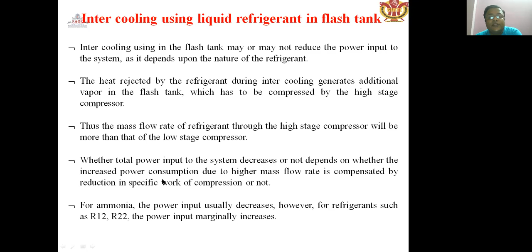Whether the total power input to the system increases or not depends on whether the increased power consumption due to the higher mass flow rate is compensated by the reduction in the specific work of compression or not. For ammonia, the power input usually decreases. However, for refrigerants such as R12 and R22, the power input marginally increases. If the power input is not to increase, the refrigerant vapor should be below the evaporator temperature. The mass flow rate through the higher stage compressor will be more than that through the low stage compressor.